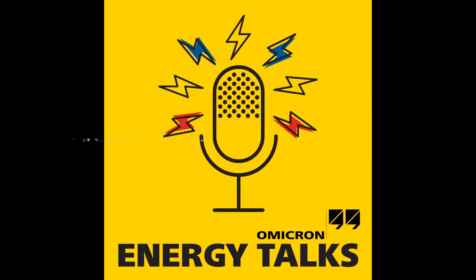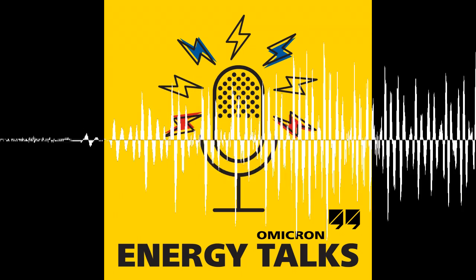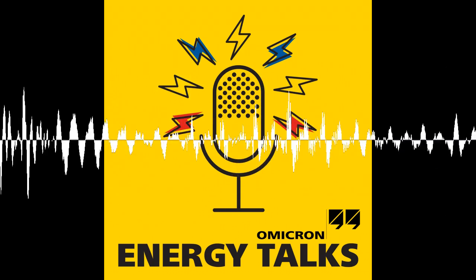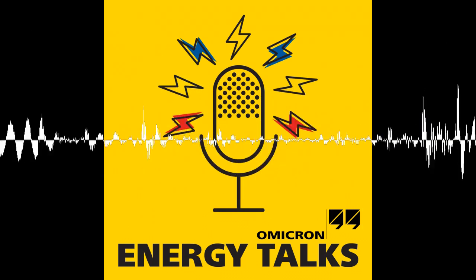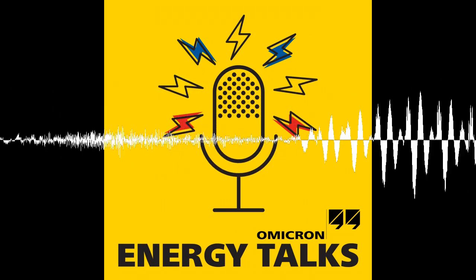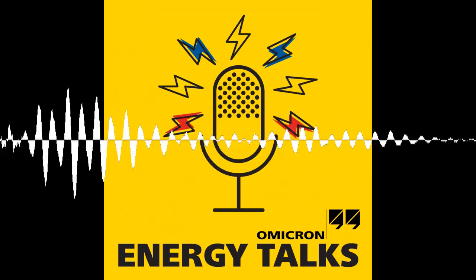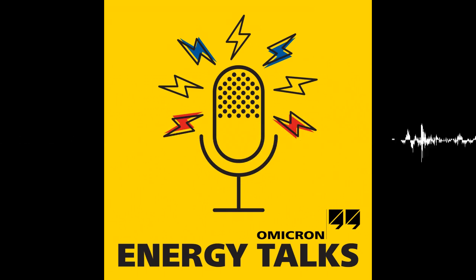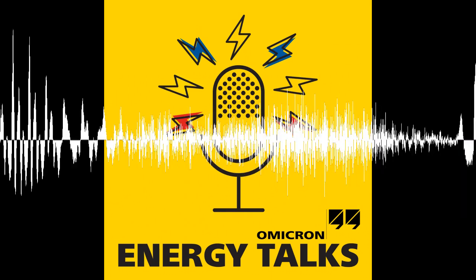And it's really happening. And I think people working on circuit breakers and testing circuit breakers really should try to follow this information and this news that's coming out. You'll hear terms now, such as a gas called G3, and you'll hear other terms like Novec and Air Plus. These are all technologies that are slowly being introduced into the North American market. And I think that this is a very good thing for us. It's going to require some changes on our behalf, but we're really going to have to see how these work and how these breakers are tested and basically learn the technologies, because it's definitely happening as we speak. Awesome. Thank you for that summary.